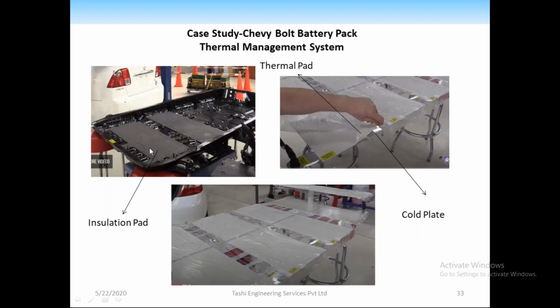This is the insulation pad, the black colored one. The black color is the chassis, a mild steel chassis of 65 kg. We don't want the cold plate to cool this chassis. We don't actually care how much this chassis gets heated, because we are concerned about the batteries. So we put the foam, the insulation pad, here, and as I stated earlier for conductive heat flux, this insulation pad also serves that purpose - my conductive heat flux into the battery is minimized.